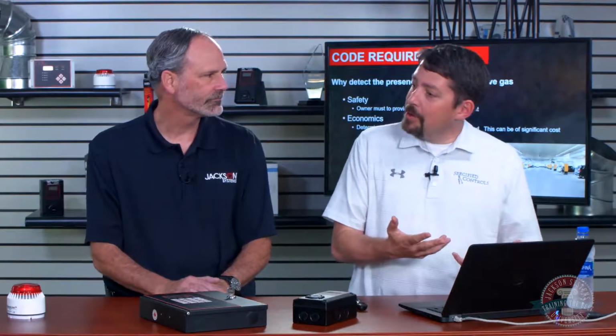Depending upon the climate, the economics of this can be expensive. If it's below ground, or that's probably not a good example, if it's an above ground parking garage in Texas, it's going to get hot in there, right? So they're going to want to run the exhaust fans to try to cycle air through there. Well, are they doing that enough? Are they not doing that enough to ventilate it? Those kind of things. So there's a lot of different pieces to this. And then continually running large fans, as we say there, is very costly.